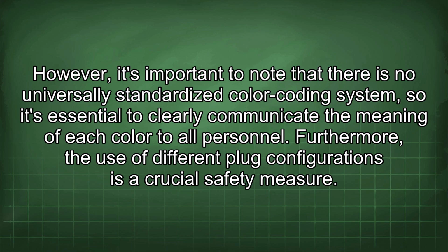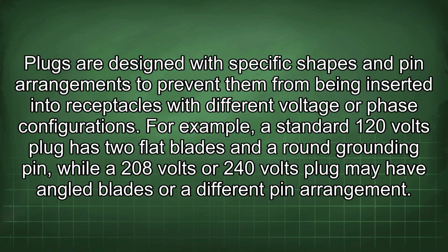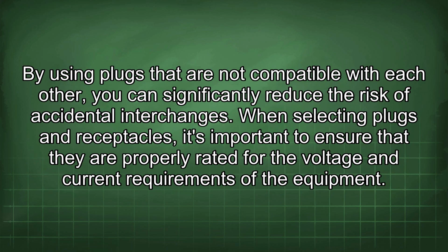Furthermore, the use of different plug configurations is a crucial safety measure. Plugs are designed with specific shapes and pin arrangements to prevent them from being inserted into receptacles with different voltage or phase configurations. For example, a standard 120-volt plug has two flat blades and a round grounding pin, while a 208-volt or 240-volt plug may have angled blades or a different pin arrangement. By using plugs that are not compatible with each other, you can significantly reduce the risk of accidental interchanges.